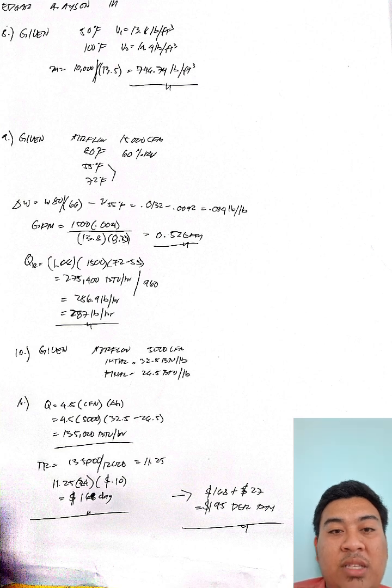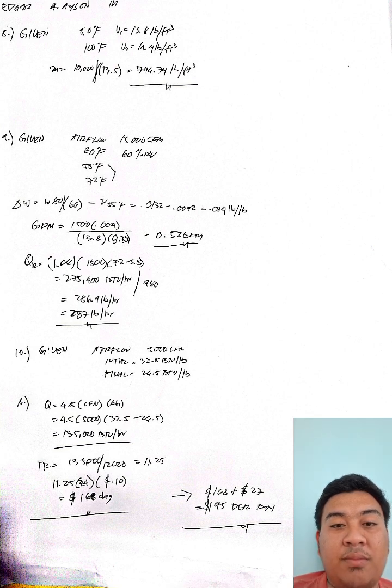To find the mass flow rate, I just use this initial condition, which is 10,000 CFM divided by 13.5 cubic foot per pound, which is equal to 740.74 pounds per hour. Now, for the HOTS part, the CFM at the final state is higher because the air expands when heated. Using the ratio of specific volume, the final CFM is equal to 740.74 times 14.9, which is equal to 11,037. It increases about 11%.